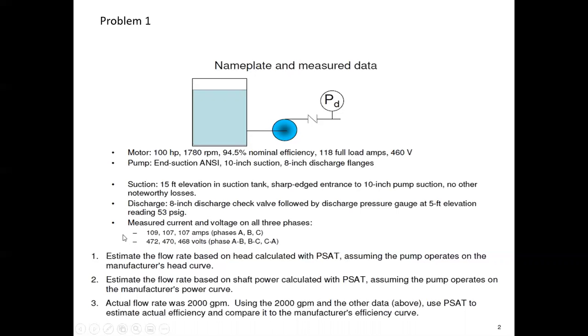So we have the electrical data, the measured current and voltage on all three phases: 109 amps on phase A, 107 on phase B, and 107 on phase C. And then the phase-to-phase voltages, 472 A to B, 470 B to C, and 468 C to A.